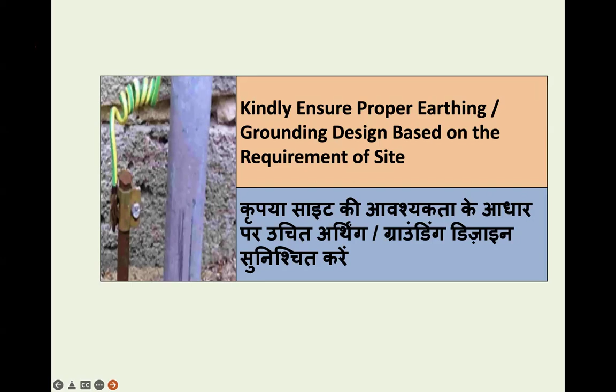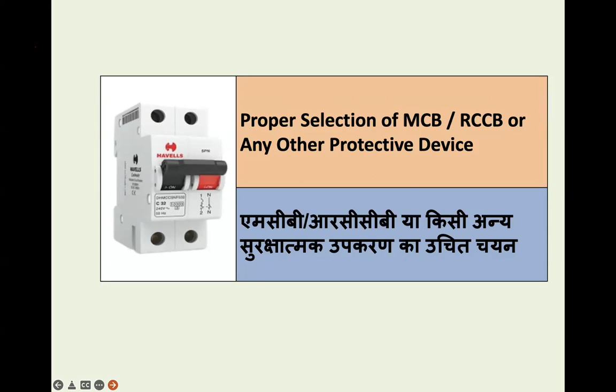There should be proper selection of RCD and MCB based on earth fault loop impedance testing and the rating of your equipment, that is called load. That will ensure your safety, and that will ensure the tripping of that MCB when required.